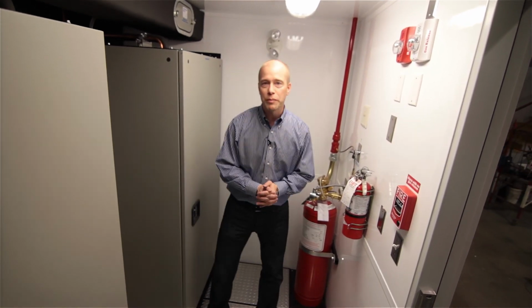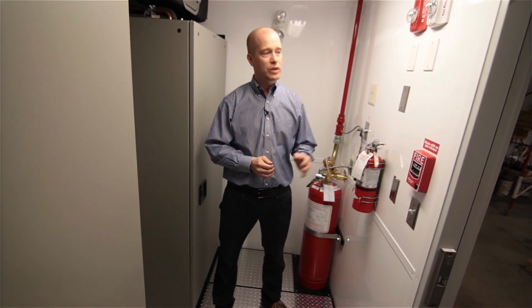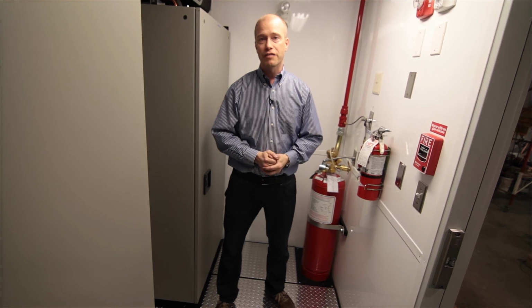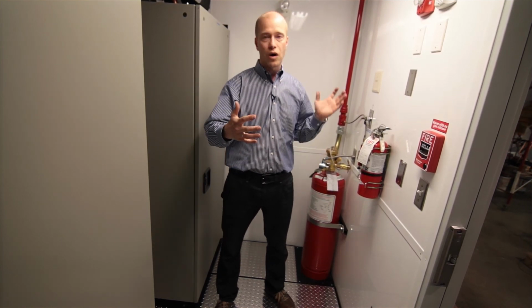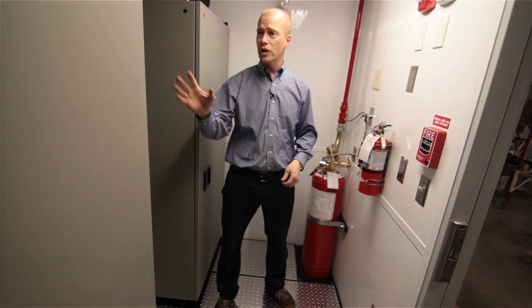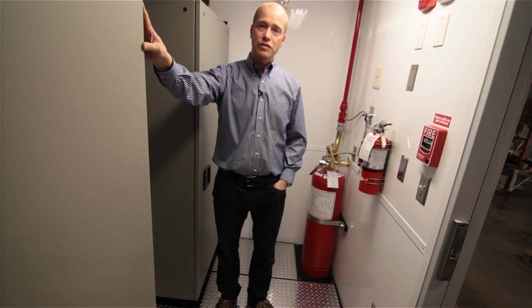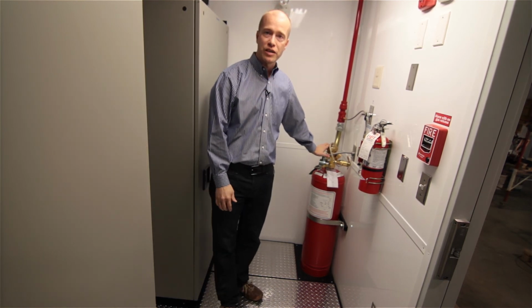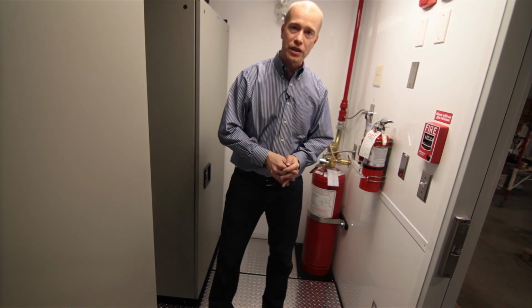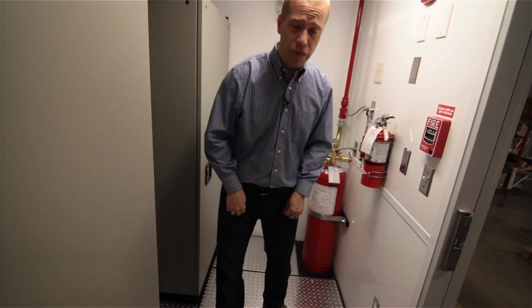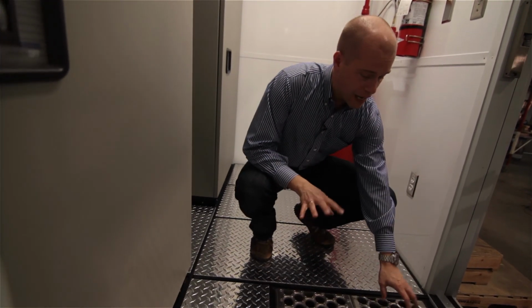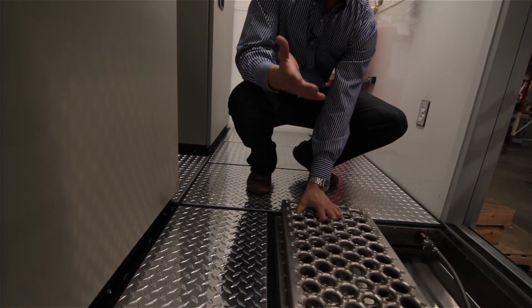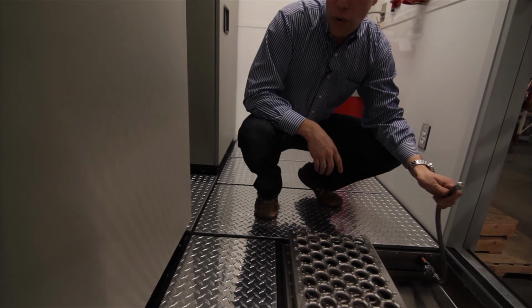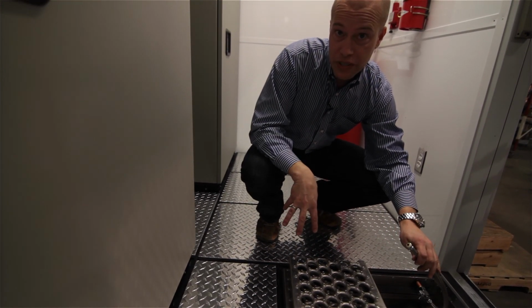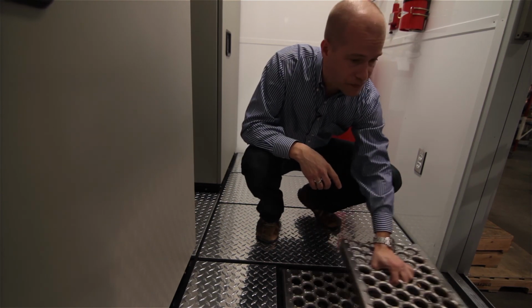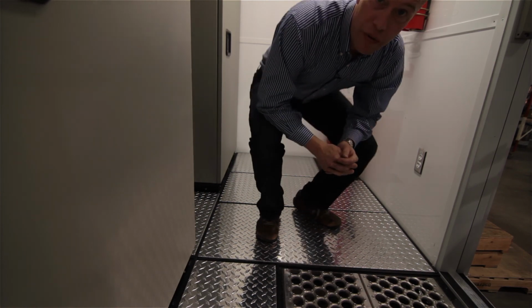We're in the vestibule, which is zone number 2. The vestibule was designed as an environmental break between the outside of the mobile data center and the inside of the data center itself. This is all part of our all-in-the-box design that makes it all fit into one 40-foot shipping container. We also have inside the vestibule redundant condensers for the air conditioning system and our Novec 1230 gas fire suppression. We also designed a feature for the mining industry, an integrated boot cleaner. So the boot cleaner is integrated into the floor, and it also has the ability to be cleaned out. So if you knock your mud off of your boots, there's a water hose that you can clean out the boot cleaner, and there's a built-in drain that can drain all the excess water. So let's go to zone number 3.